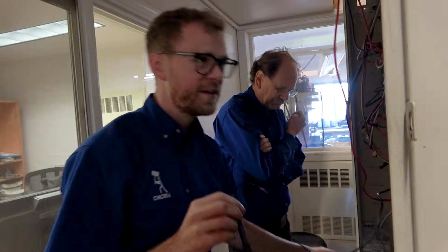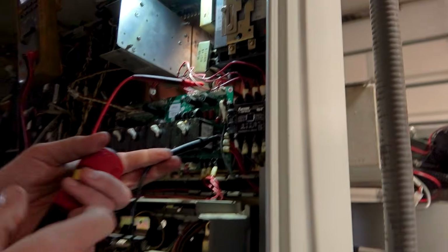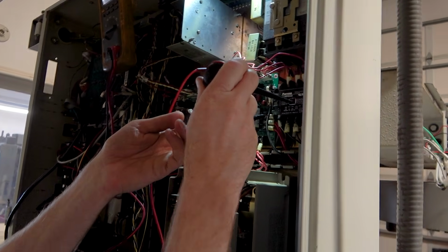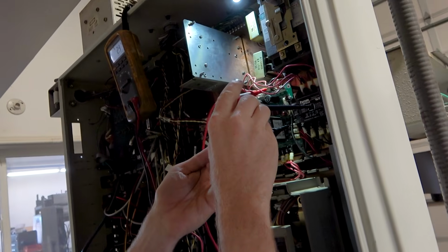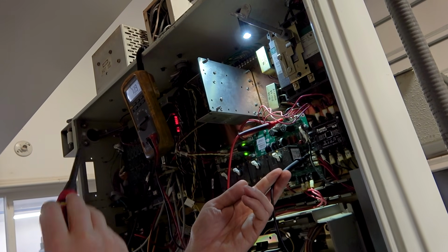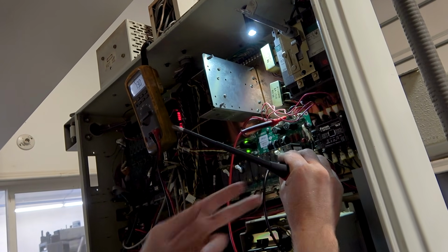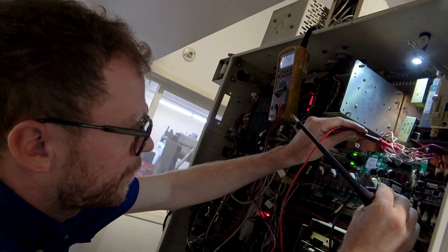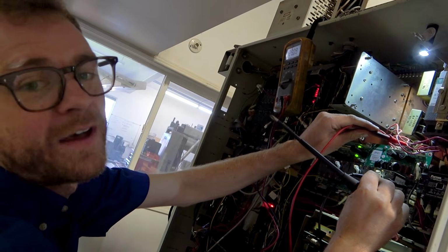When you press this in, let's do it real quick. I'm going to put my voltmeter here, using an insulated screwdriver, and if I push this in, the machine - if it's functioning correctly - should latch. Now I've got no voltage across it because I'm measuring on the same line. If I change my ground reference, now I've got 28 volts.